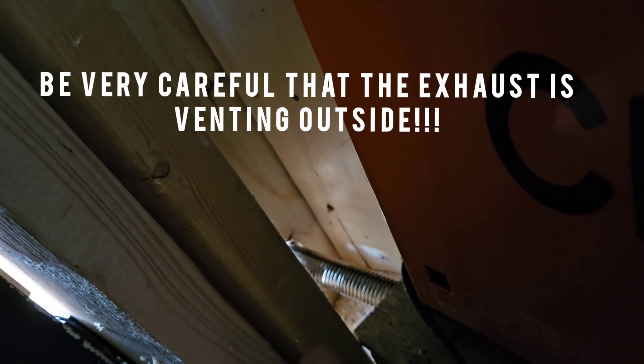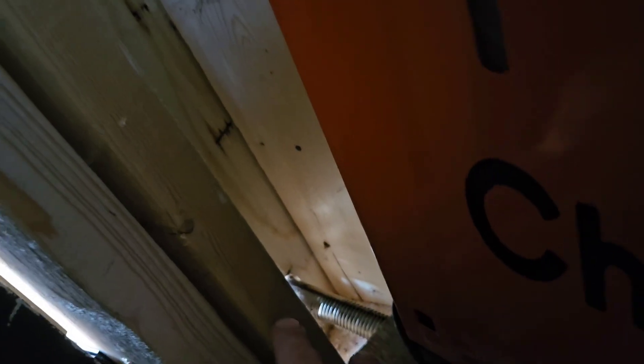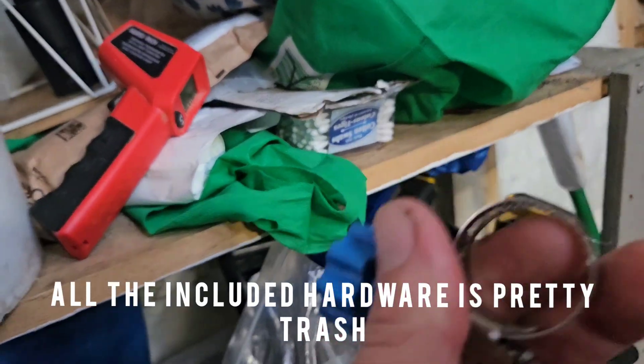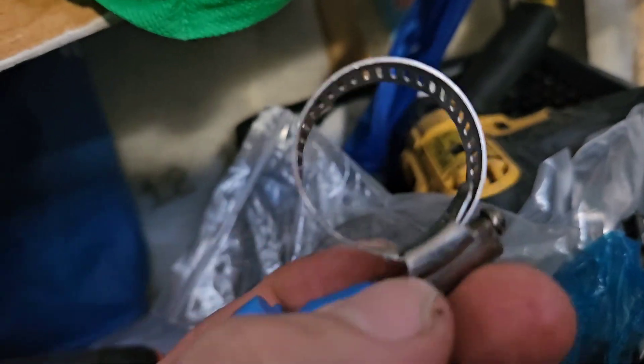final solution or final enclosure, but this is just so it's not venting inside. You do not want to mess with carbon monoxide—it will kill you, especially in a place this small. So be very, very careful to make sure it's venting properly out the door. Make sure it's connected because the hardware they supply is absolute garbage. This is one I have that I'm going to install that is better. But they just install these really cheap rings—I don't know what they're called—and they suck. So you absolutely want to make sure that this is connected and doesn't fall off.